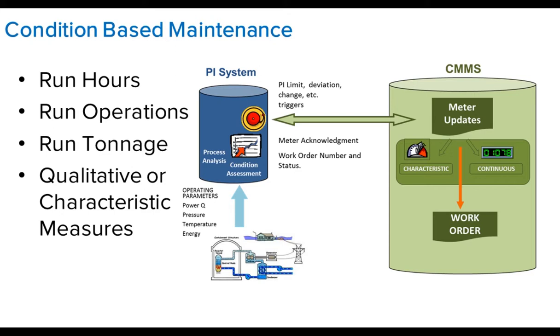So in this typical case, you're changing preventive maintenance from calendar-based to condition or usage-based. In many cases this is based on runtimes, such as compressor runtimes or operations like breaker operations. You could have start and stop cycles on pumps, or even material process measures, such as tonnage on a conveyor belt. There are many different ways to take that type of data and make it qualified.